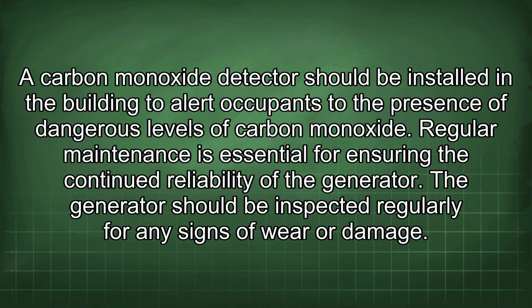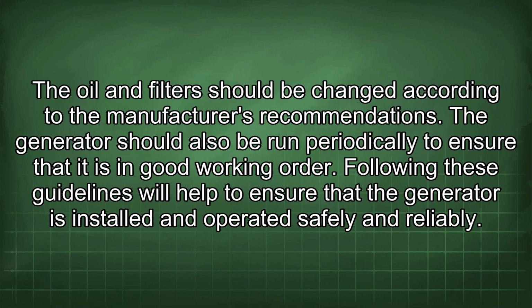carbon monoxide. Regular maintenance is essential for ensuring the continued reliability of the generator. The generator should be inspected regularly for any signs of wear or damage. The oil and filter should be changed according to the manufacturer's recommendations. The generator should also be run periodically to ensure that it is in good working order. Following these guidelines will help to ensure that the generator is installed and operated safely and reliably.